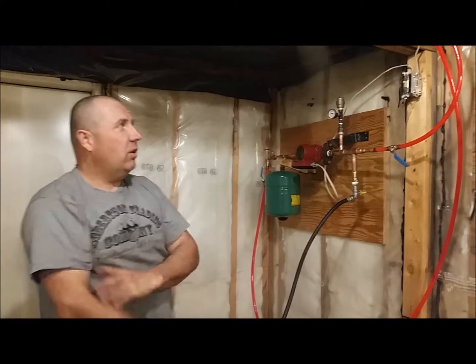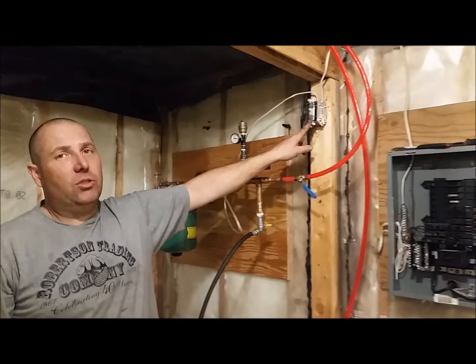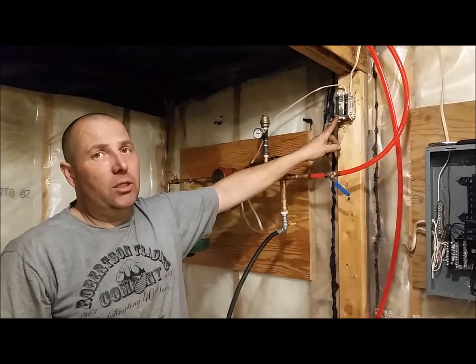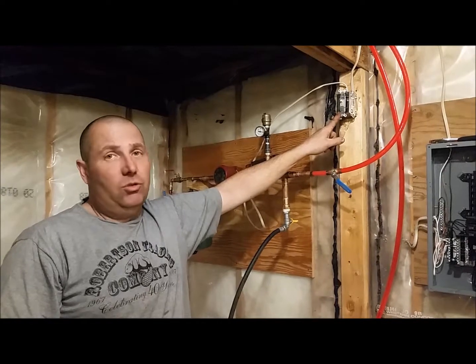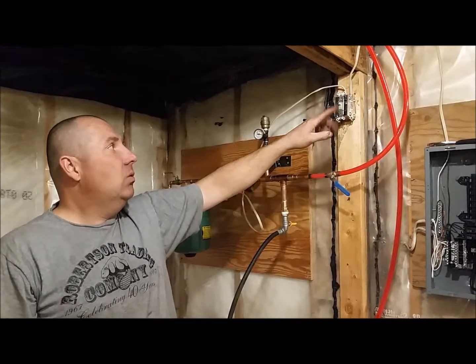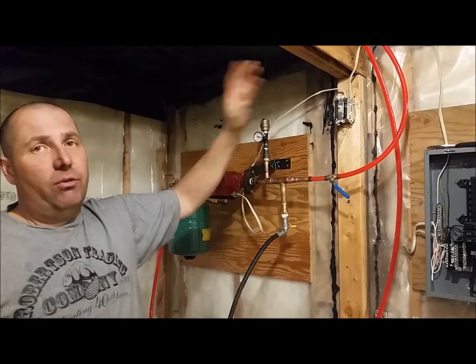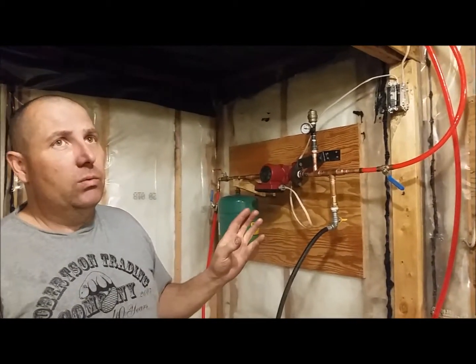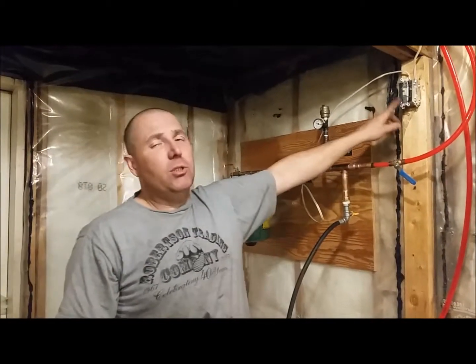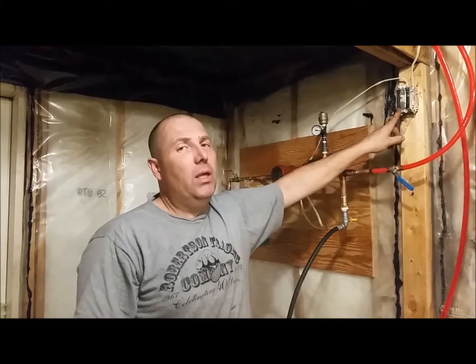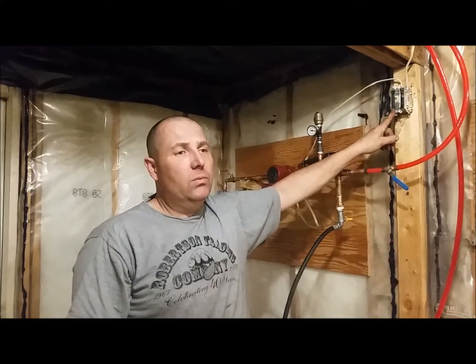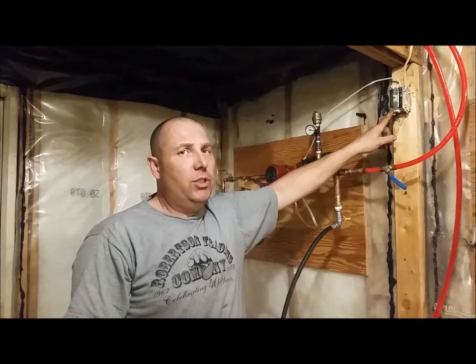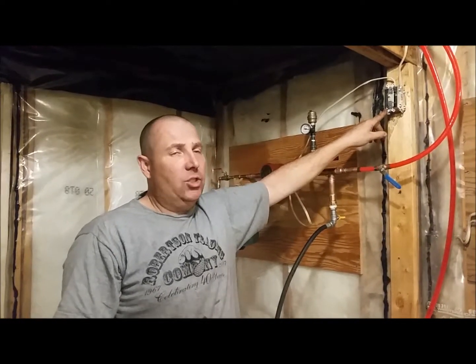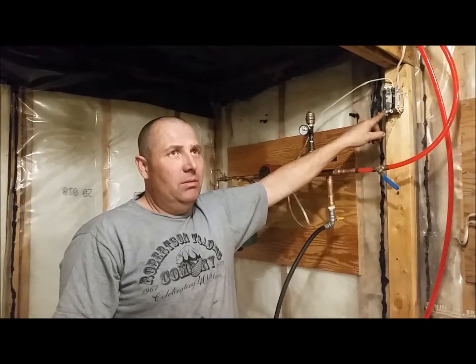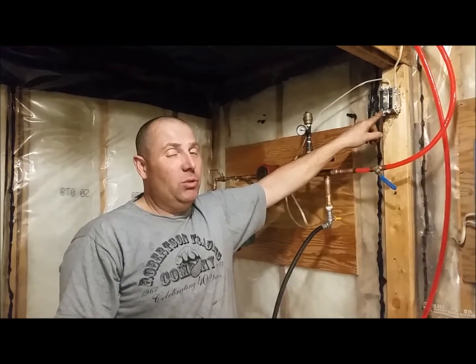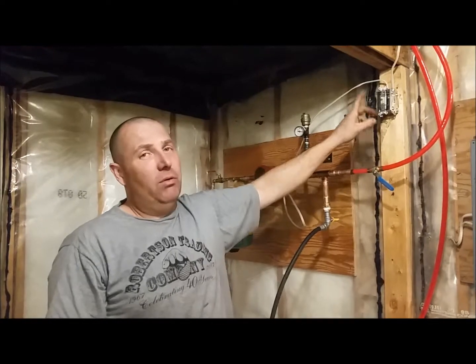So basically we'll start here. We have a master kill switch. So basically this turns on and off the pump. The pump is just a circulating system. So shutting that off, the water no longer circulates. For safety reasons, we need to keep this circulating as long as we have a fire going. Basically, we want to avoid steam generation and overheating in the heat exchanger. That can end up in an explosion in the heat exchanger, and we want to avoid that at all costs.